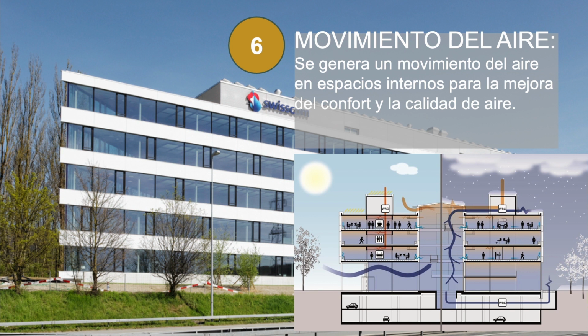And it's an example of how to use natural ventilation together with mechanical ventilation, using the atrium of the building as a lung. So we provided night cooling, night flush. We had the soil underneath the building as a thermal storage and the cooling source. And it resulted that the energy demand for mechanical ventilation was at the lowest level.